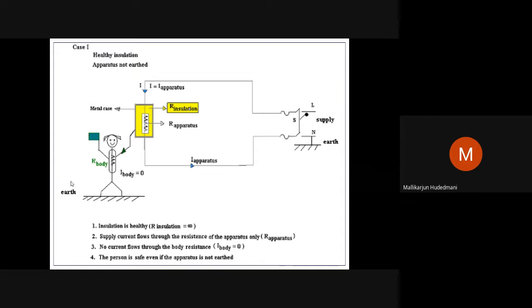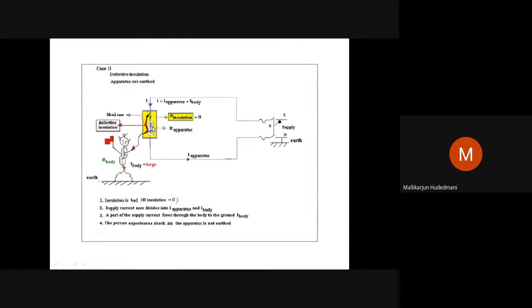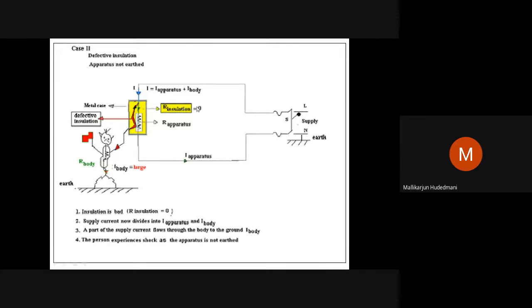Over years of usage, what may happen? This device develops internal loss of insulation, leakage, etc. You can see here, the apparatus is not earthed. Even there is no earthing, 2 pin. I used it for the past 2 years, 3 years, but the device has developed an aging effect. The insulation property of it is lost. When I touch it, I may feel an electric shock. This is how the person who touched it earlier did not feel it, but now he is feeling electric shock. This is because the insulation of the device has degraded, the aging effect has come, and internal faults might have developed. That made the live part or metal enclosure, when he touched it, make him a path for the current to flow, and the person experiences electric shock. Depending upon the amount of current flowing through his body, the severity can be determined.